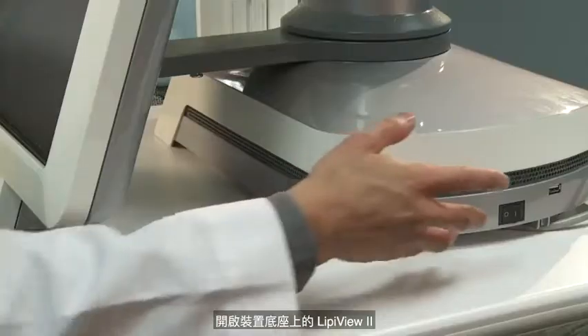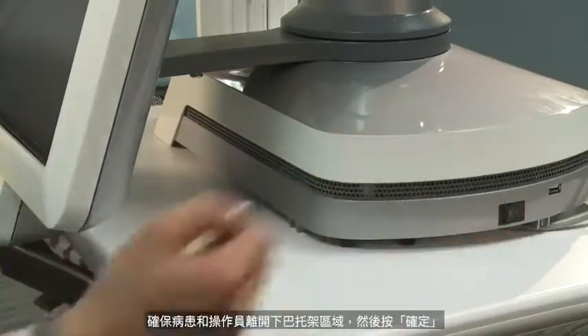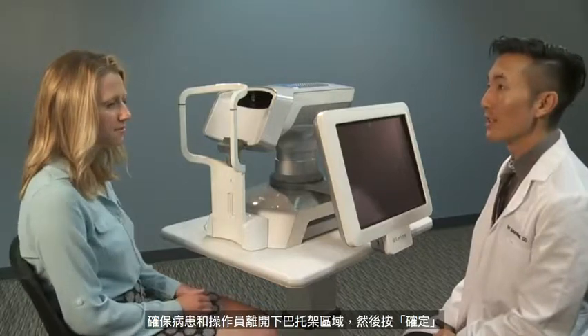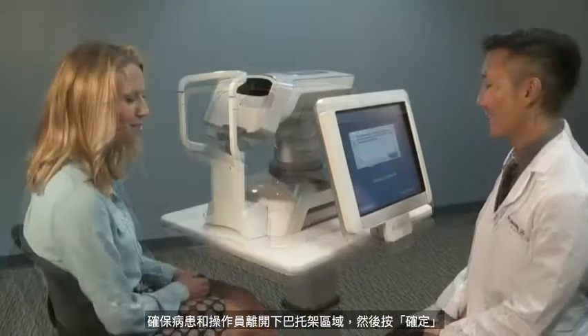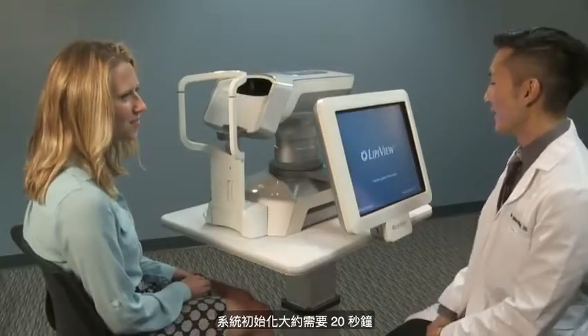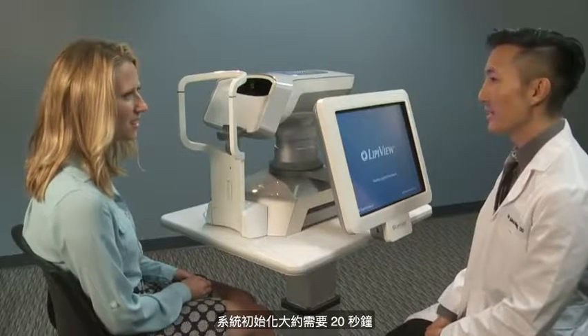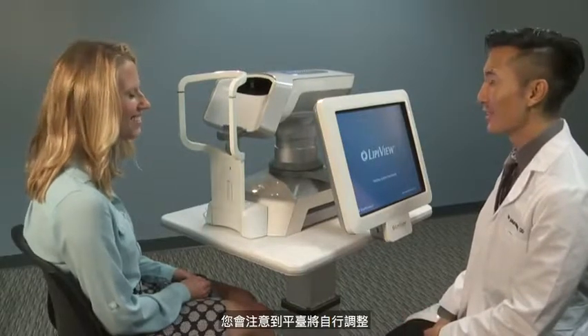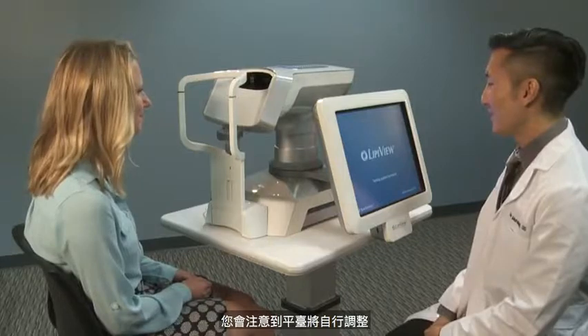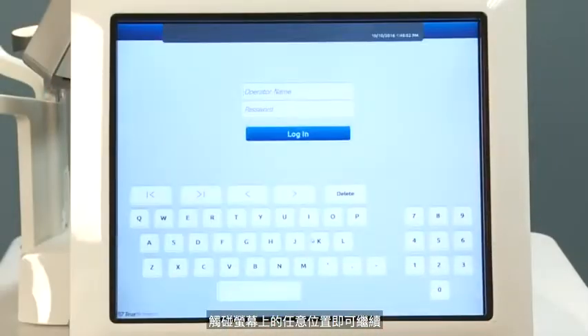Power on LipiView 2 at the device base. Ensure the patient and operator are clear of the chin rest area and press OK. The system initialization will take about 20 seconds. You will notice the motion stage will self-adjust. Touch anywhere on the screen to continue.